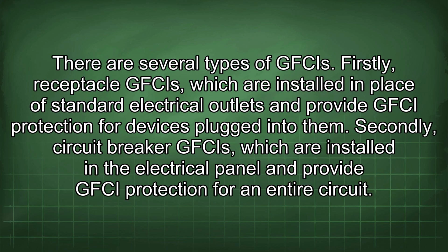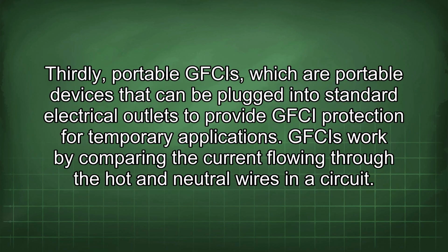There are several types of GFCIs. Firstly, receptacle GFCIs, which are installed in place of standard electrical outlets and provide GFCI protection for devices plugged into them. Secondly, circuit breaker GFCIs, which are installed in the electrical panel and provide GFCI protection for an entire circuit. Thirdly, portable GFCIs, which are portable devices that can be plugged into standard electrical outlets to provide GFCI protection for temporary applications.